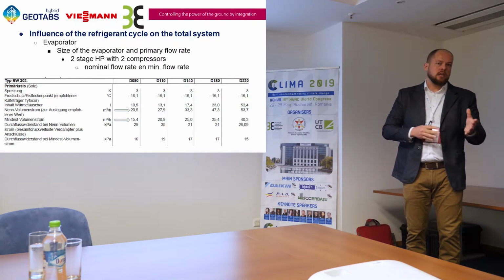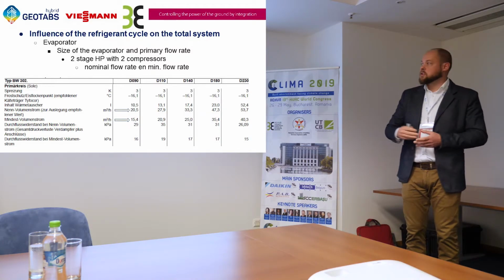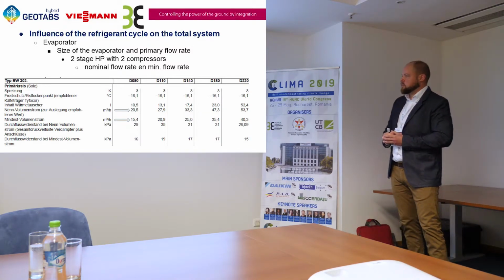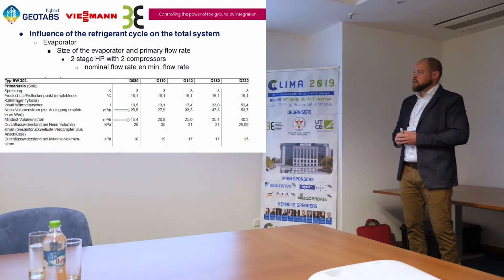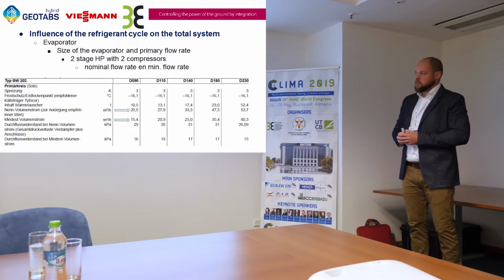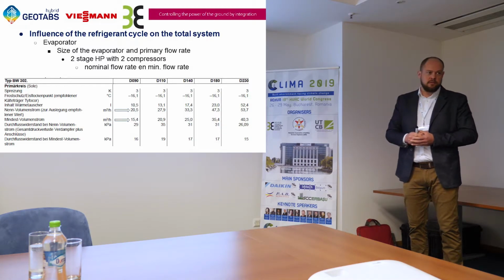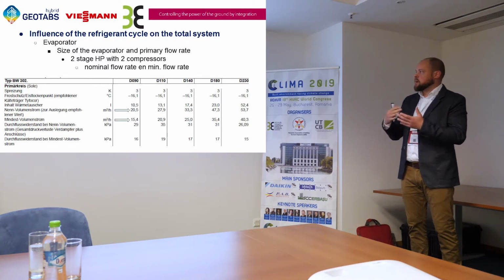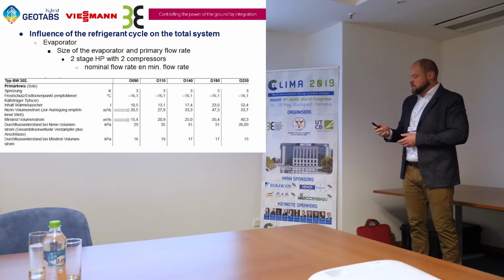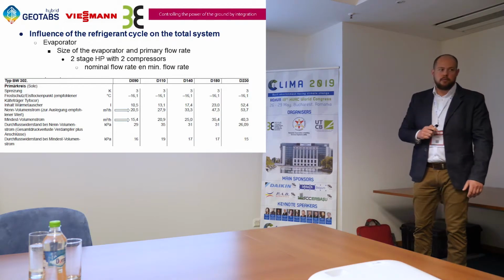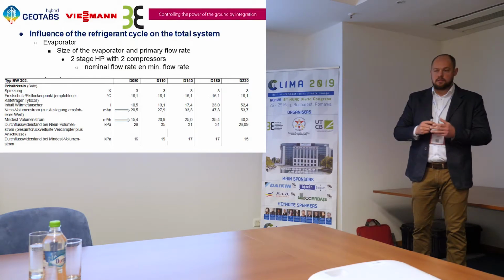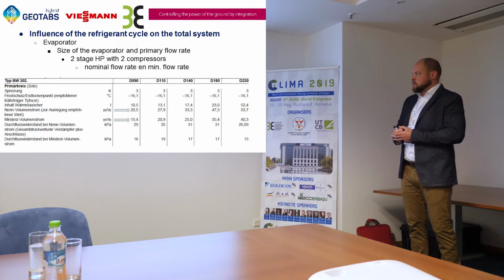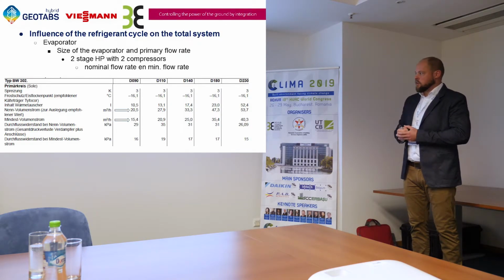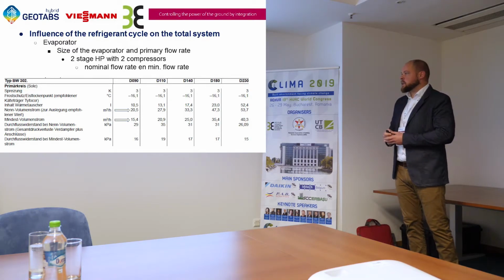So we can control the output power in two steps. For example, at 90 kilowatts, it will make about 85 kilowatts on two stages. And when we switch to one stage, it will be about 40-45 kilowatts. So this is one way of regulating the power, but a very important aspect is also the flow rate on the evaporator side of the source. So the mixture of glycol in the source is flowing through the source, but also through the evaporator, and we have to maintain a minimum flow.